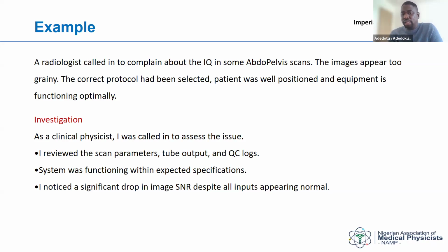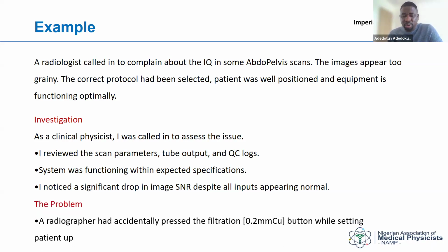But for me, I can also look at the image. There's something we call the DDI, or the exposure index, that will tell you about the signal to noise ratio on that exposure. If you notice a significant drop in your image SNR, then you can tell that something is blocking the radiation. Something has happened between the exit of the radiation from the tube and the detector. Then you can tell. So, from there, what is the problem?